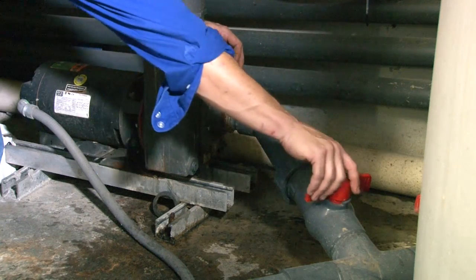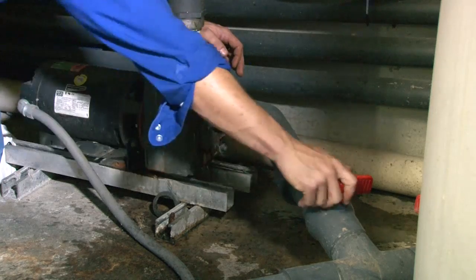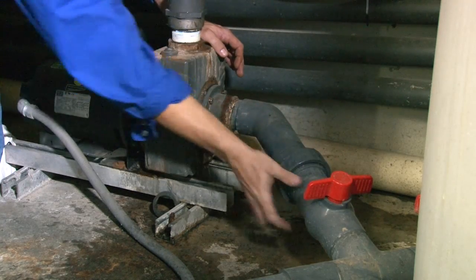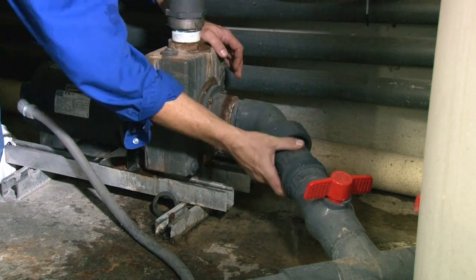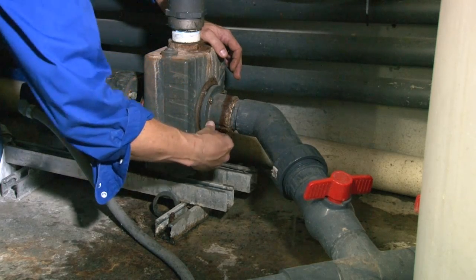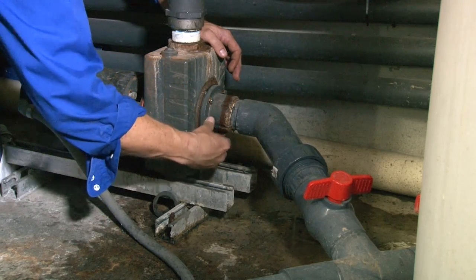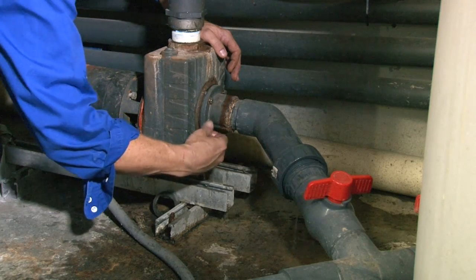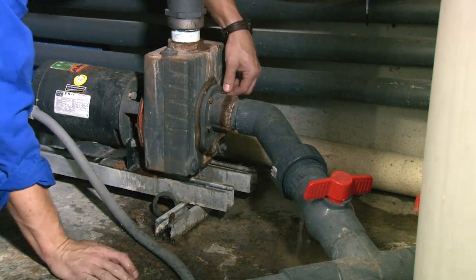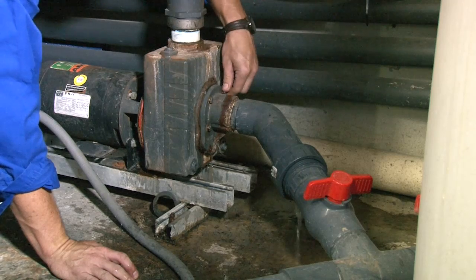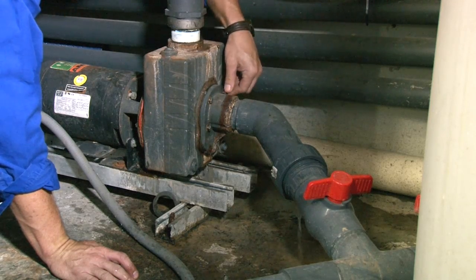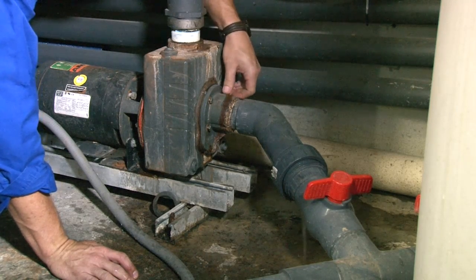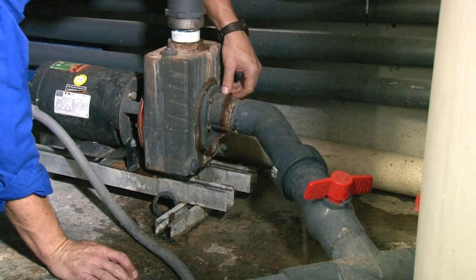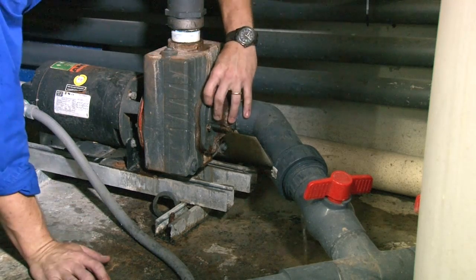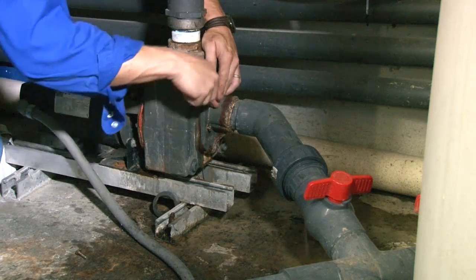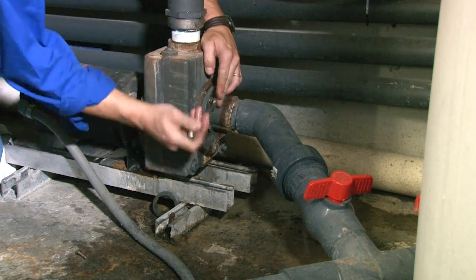So the first thing I would do is always just close off the inlet ball valve that goes down to the pit. Open up the connecting union, and then pull out the 6 bolts that hold the inlet pipe onto the pump. And these are all 7/16. And if you're lucky, your clog's only right at the inlet. So this is always the first line of defense.